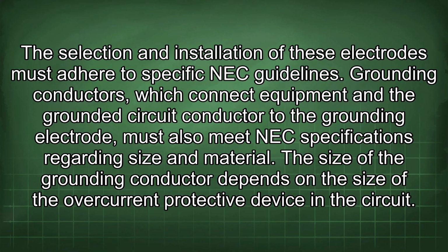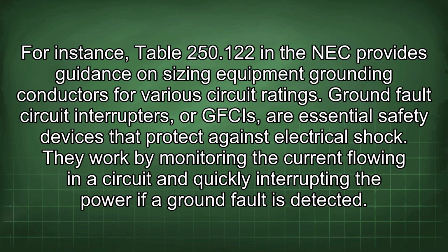Grounding conductors, which connect equipment and the grounded circuit conductor to the grounding electrode, must also meet NEC specifications regarding size and material. The size of the grounding conductor depends on the size of the overcurrent protective device in the circuit. For instance, Table 250.122 in the NEC provides guidance on sizing equipment grounding conductors for various circuit ratings.